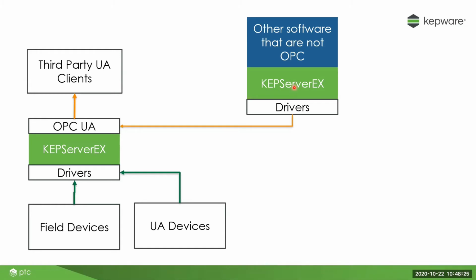The other thing is you could be using something like iFix today that's still using OPC DA. You can use the KEP server to pull in and aggregate data, then expose that data out again via classic OPC. So you can reuse your classic OPC software and licensing - things you're familiar with, you don't have to relearn everything.